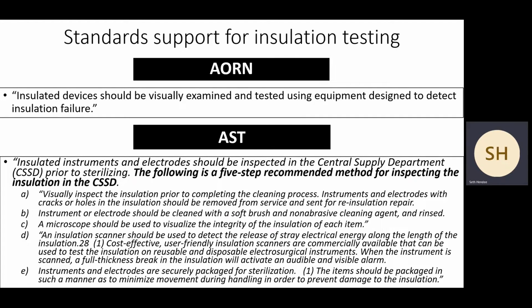AST recommends the following 5 steps for inspecting their insulated instruments in the CSSD. Visually inspect the insulation prior to completing the cleaning process. Instruments or electrodes should be cleaned with a soft, non-abrasive brush, so they're trying to prevent damage there. A microscope should be used to visualize the integrity of insulation of each item. So they're saying, look, your regular eye cannot do this. It's not capable of seeing some of these very small damages. So to go on, an insulation scanner should be used to detect the release of stray electrical energy along the length of the insulation. Right. There you go. So they're trying to very much enhance your optical inspection by calling out a microscope, and then still saying, well, why don't we use one of these devices on the market that is able to detect insulation leakage? Instruments and electrodes are securely packaged for sterilization.